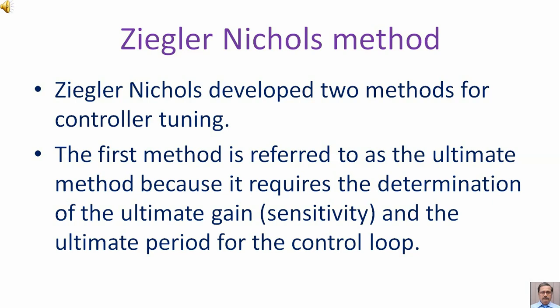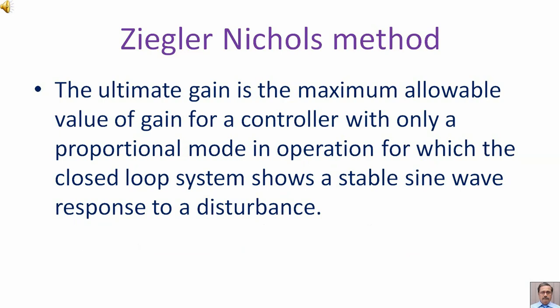The ultimate gain is the maximum allowable value of gain for a controller with only a proportional mode in operation for which the closed-loop system shows a stable sine wave response to a disturbance.